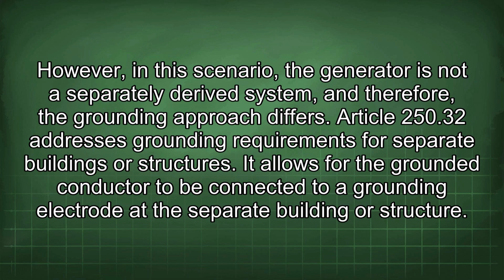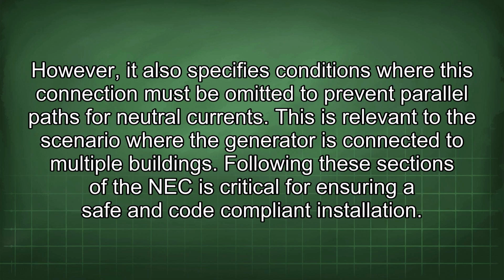Article 250.32 addresses grounding requirements for separate buildings or structures. It allows for the grounded conductor to be connected to a grounding electrode at the separate building or structure. However, it also specifies conditions where this connection must be omitted to prevent parallel paths for neutral currents. This is relevant to the scenario where the generator is connected to multiple buildings. Following these sections of the NEC is critical for ensuring a safe and code-compliant installation.